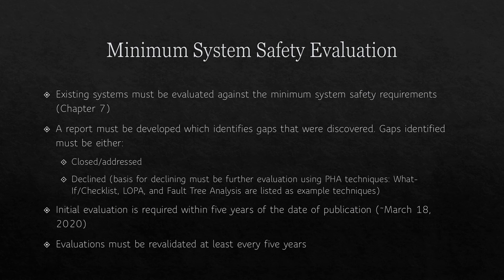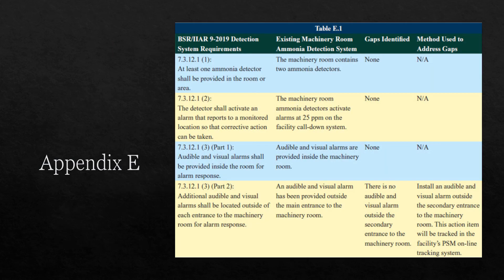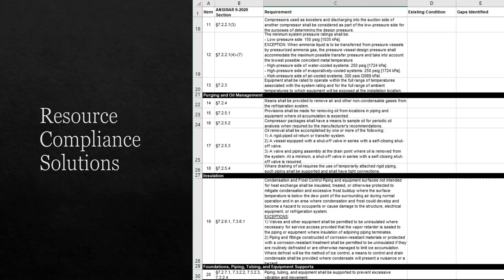Evaluations must be revalidated every five years. Existing systems must be evaluated against the minimum system safety requirements in Chapter 7, and a report must be developed identifying any gaps discovered. Gaps must be either closed by complying with Chapter 7 or declined after demonstrating further evaluation using a PHA technique. Appendix E contains an example safety evaluation format. We will likely be performing evaluations in conjunction with PHAs and including the documentation in the PHA report.